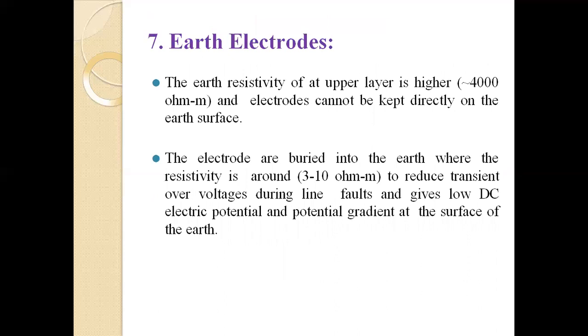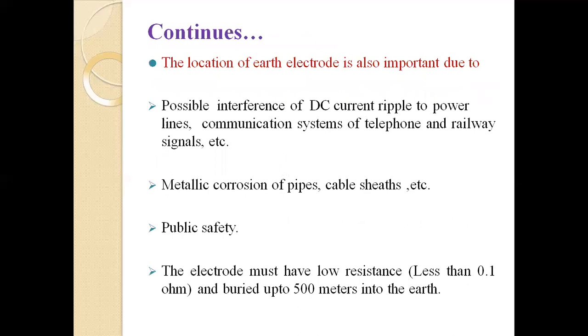Next part is the earth electrode. The earth resistivity at the upper layer is higher, about 4000 ohm meter, and the electrode cannot be kept directly on the earth surface. The electrodes are buried into the earth where the resistivity is around 3 to 10 ohm meter, to reduce transient overvoltage during line faults and give low DC electrical potential and potential gradient at the surface of the earth. The location of the earth electrode is also important due to the possible interference of the DC current ripple to the power lines, communication systems of the telephone and railway signals, etc.